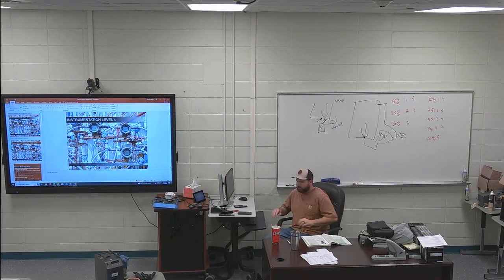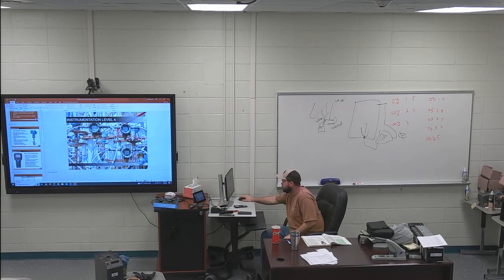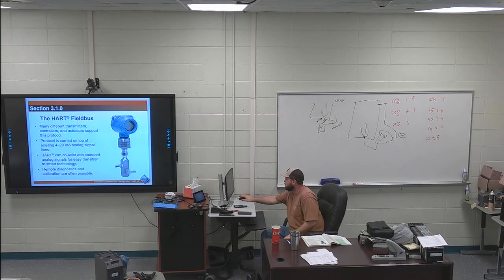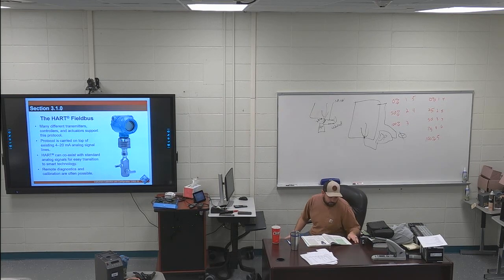Smart transmitters. You probably have heard of HART communication. I don't ever remember, it says highway addressable remote transducer. This is just a way of talking to different transmitter controllers. So you can talk to most transmitters through HART communication, no matter what the brand is. It's just a way of communicating over a 4 to 20 milliamp signal. Very, very useful. A lot of stuff is HART compatible.